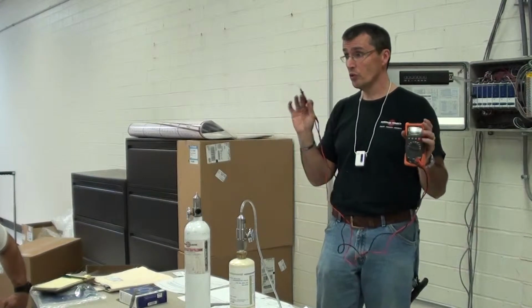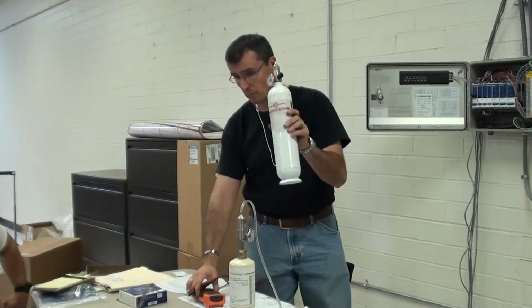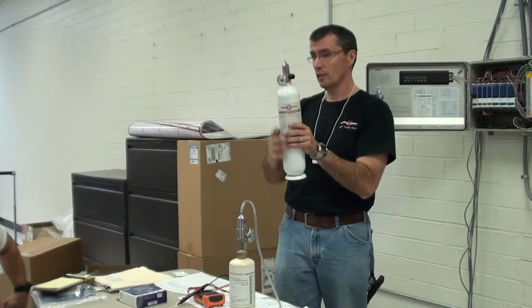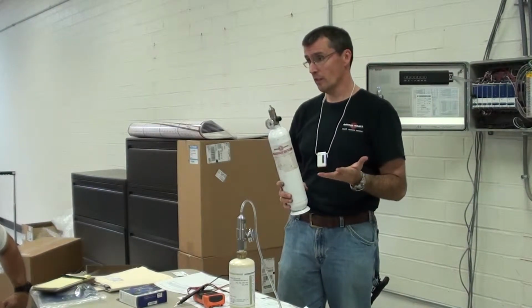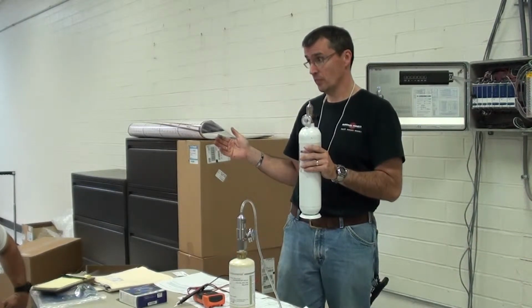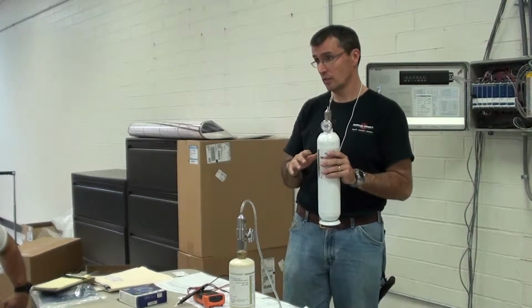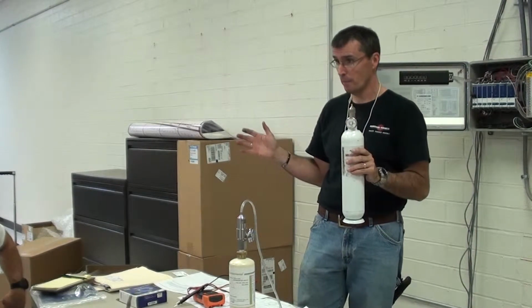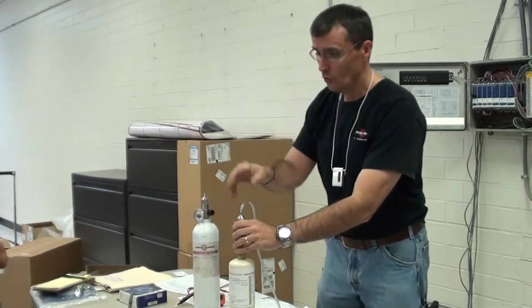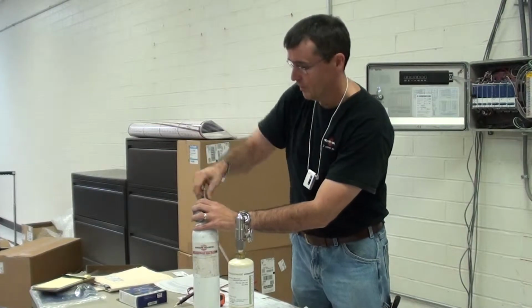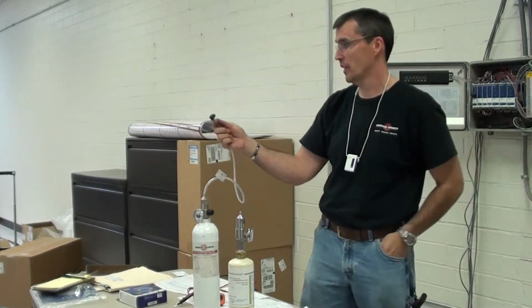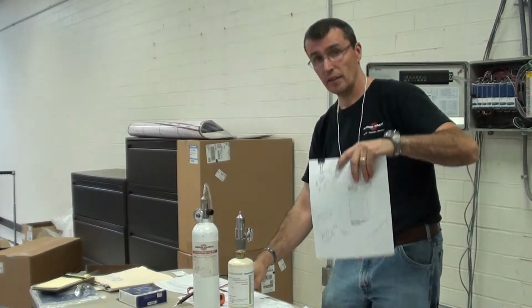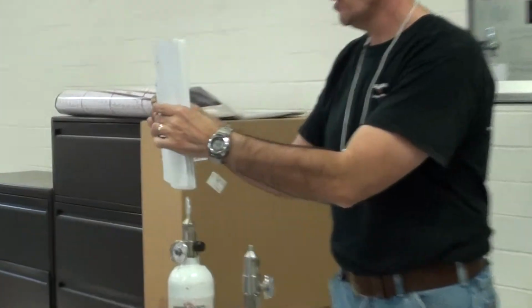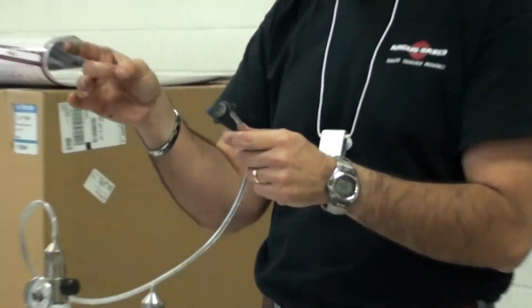Okay? So when you do your zero, which is what you do first, you're going to apply your calibration gas. When you get the cylinder, you'll screw on a regulator. And the regulator will need to be either a 0.5 liter per minute or a 1.0 liter per minute regulator. That's the flow rate you want to use for calibrating an Xgard. So you can use anywhere between a 0.5 and a 1.0. Alright? So you'll take your regulator and attach a hose to it. And at the end of that hose, you'll have what we call a calibration adapter. This calibration adapter, I know you can't see this real well, but it slides right into the nose section of the Xgard. So when you open up the cylinder, it passes gas through your tubing, through your calibration adapter, and saturates that little compartment where the sensor is.